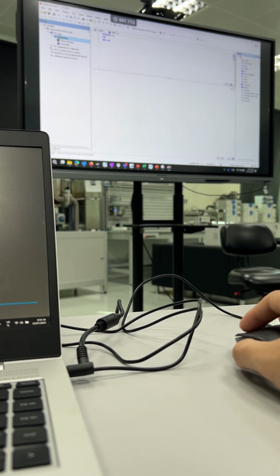Okay. Yeah, sure. Then for application here, after you add a program, it actually doesn't run it because there is no task for it. A task means that it's a cyclic task that the PLC will run. So what you need to do is right click on application, add object, and then add a task configuration. Then there will be a task here.